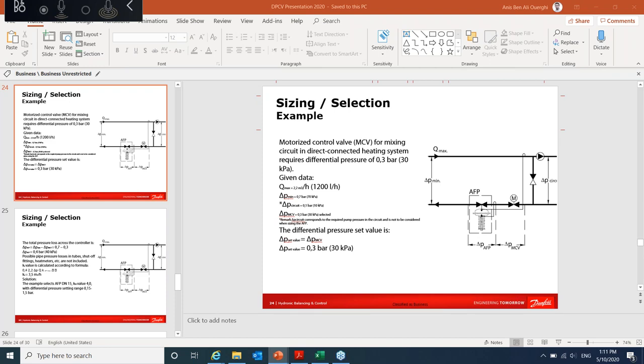Here we spoke about DPCV mainly for shopping malls and shell and core projects where you don't know what the tenant will be using. But if you have the choice to use either DPCV plus 2-way valve or PICV, I'm recommending 100% to go with PICV for sure.